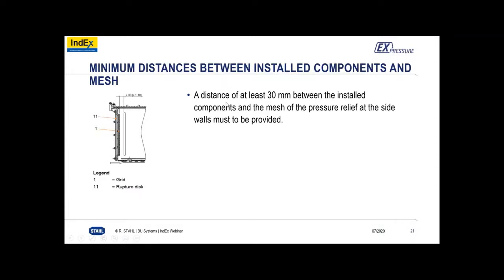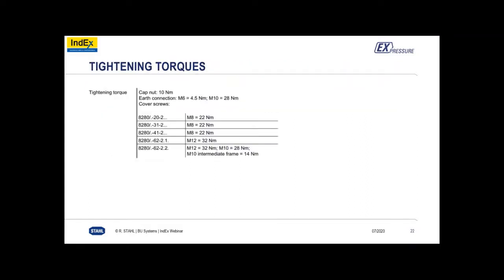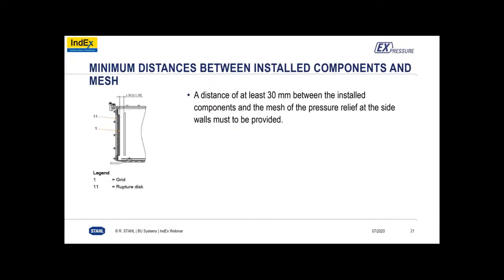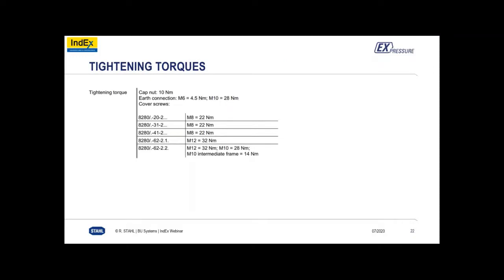So minimum distances between installed components: a distance of at least 30 millimeters between installed components and the mesh. So clearly you would say that it's because the mesh needs to have a clear path for the gas or that explosion to go directly at it, so that there's no pressure piling or restriction of that path, correct? Yes, that's correct. And here is also the maximum cross-sectional area, in the case of 2B, for example, of 80%, which must also be observed. Okay, so that the enclosure is not fully installed and the mesh is not blocked.